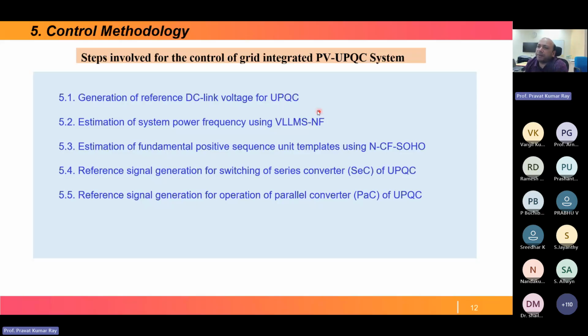So the steps are: estimation of system power frequency using VLLMS notch filter, estimation of fundamental positive sequence unit template using N-CF-SOHO, then reference signal generation for switching of the series converter, as well as reference signal generation for switching of the parallel or shunt converter. These are the different steps.